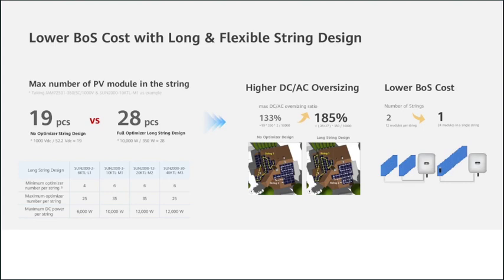If one optimizer is equipped on each module, the design rules change. We are changing from the typical voltage limitation on the input side of the inverter to a power limitation on the number of modules. So typically you divide the maximum DC power per string that we allow by your module power class. For a 3-phase inverter up to 10 kilowatt, it's 10 kilowatt per string, and this is the new limitation. We shifted this limit from 1000 volt to 10,000 watts, and the calculation is then quite easy.